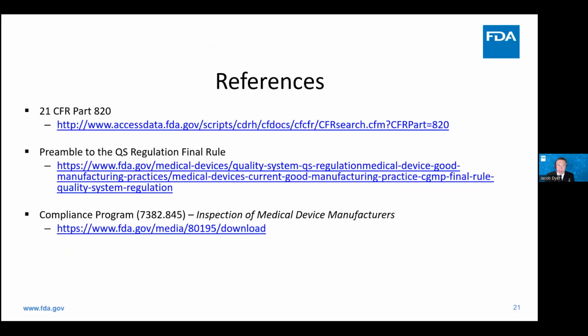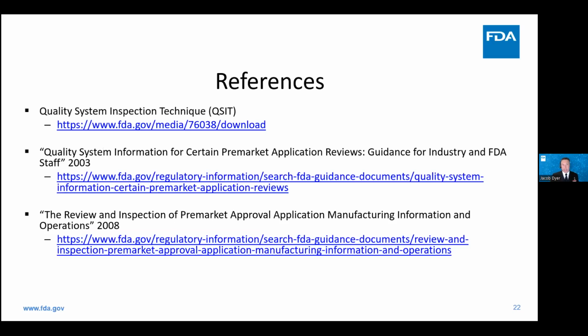So for some additional information, I'm going to provide additional references. 21 CFR Part 820, the preamble to the QS regulation final rule. I find this a great document because it gives the thinking behind the regulation. The compliance program 7382.845, and that's for inspections in general. The quality system inspection technique guide, and then there's also a guidance document for pre-market application reviews, which is listed here. And then the review and inspection of pre-market approval application manufacturing information and operations as well.